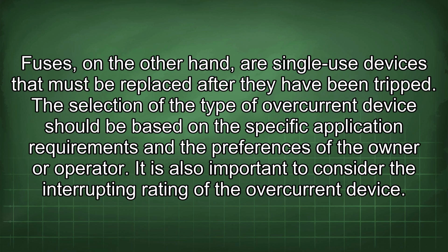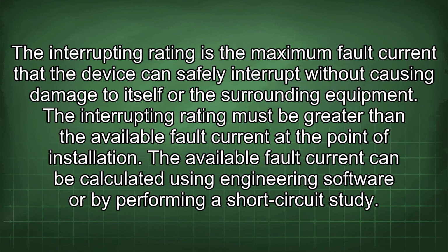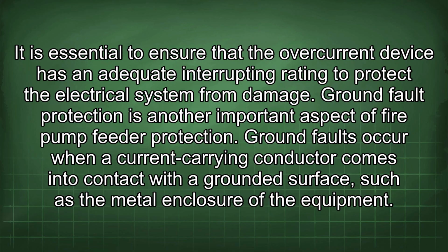It is also important to consider the interrupting rating of the overcurrent device. The interrupting rating is the maximum fault current that the device can safely interrupt without causing damage to itself or the surrounding equipment. The interrupting rating must be greater than the available fault current at the point of installation. The available fault current can be calculated using engineering software or by performing a short circuit study. It is essential to ensure that the overcurrent device has an adequate interrupting rating to protect the electrical system from damage.